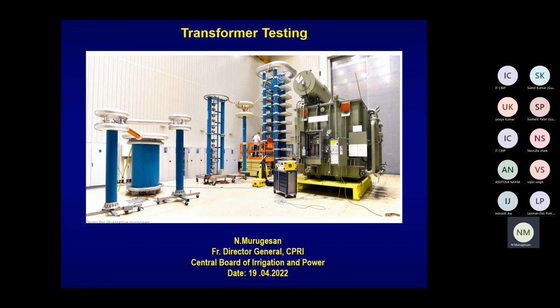If a transformer fails, whatever the time duration before you bring a new transformer or replace it, to that extent the customer will get affected. One is customer dissatisfaction, then productivity loss, and third the distribution company loses its revenue. So now distribution companies have started monitoring the transformer continuously - you have a monitoring center that will say where the transformer is overloaded, which phase is loaded, what level, all such things, so you will be able to take action to distribute the load or disconnect it.